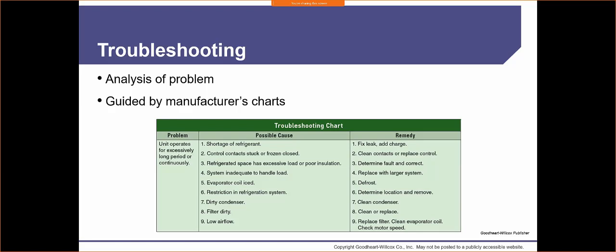So when you pull up that service manual, it's going to tell you all the information that you need, how to adjust the system based on gas pressure or adjusting the airflow, because those are things that we want to do. But secondly, there's going to be a troubleshooting chart. The troubleshooting chart is just going to be a little indicative of what we have going on. What's the possible cause, or what's the problem? Unit operates for excessively long period or continuously. Well, we may have a refrigerant leak. All right, well then how do we fix that? Well, we have to find the leak and add charge.